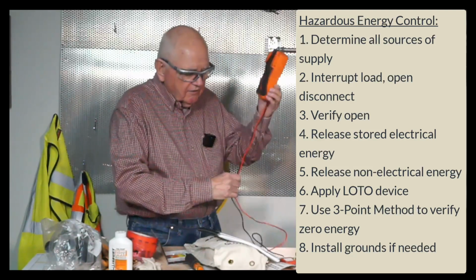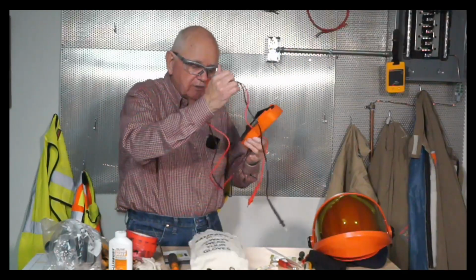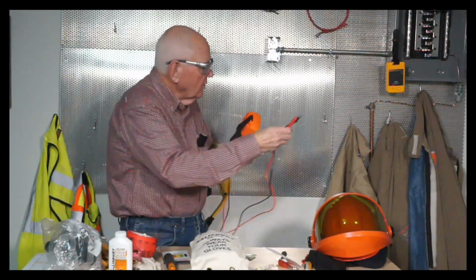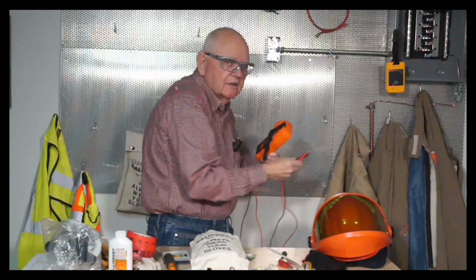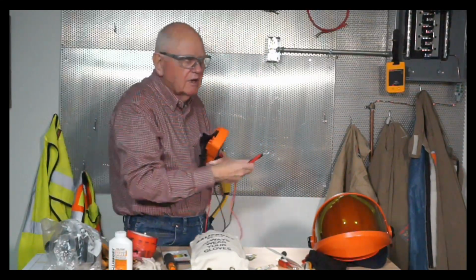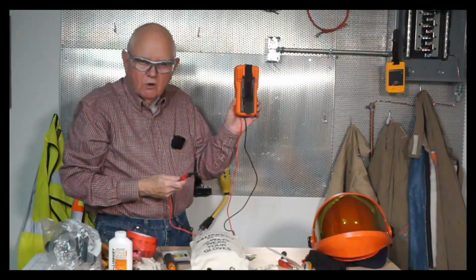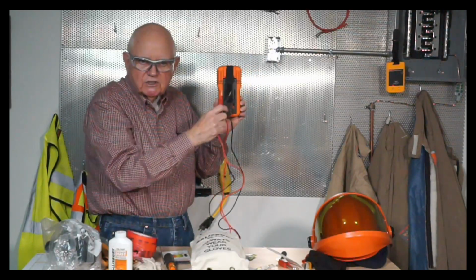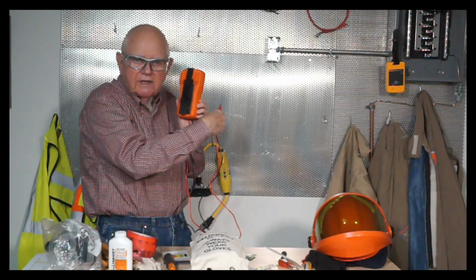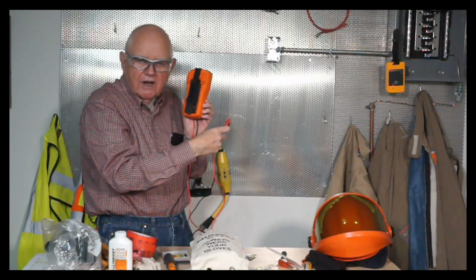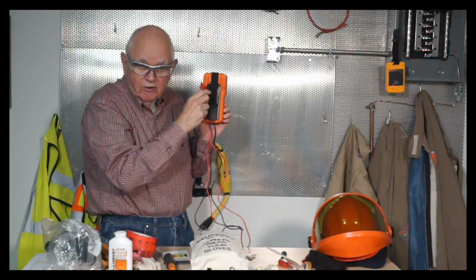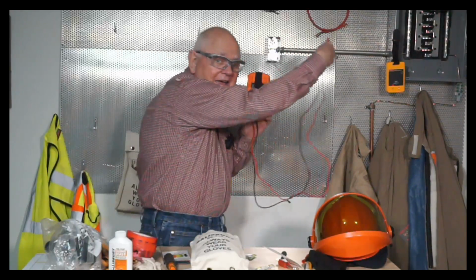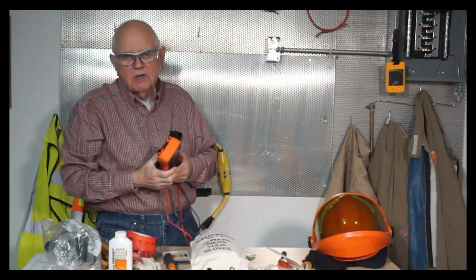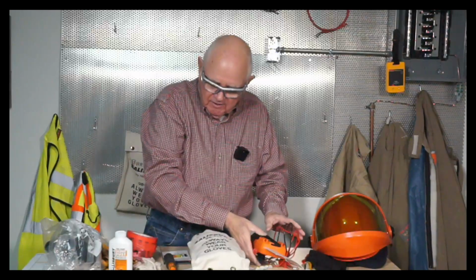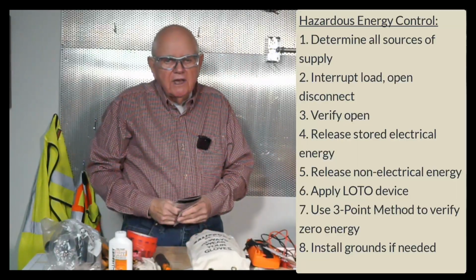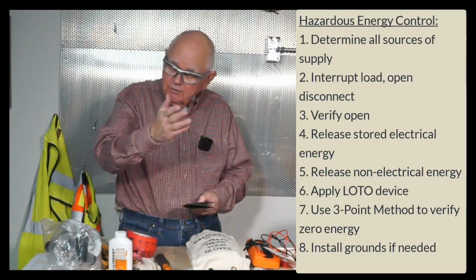And that's where you use that 3-step method, right? And a little bit of what we talked about earlier. I go through and I use my proving unit. In this case, I would go through and use my proving unit and make sure that my meter works. So I check a known source of voltage, make sure my meter works on voltage. Then I go in and I verify phase to phase and phase to ground that I have zero energy according to my meter. Then I go back to my known voltage source and make sure that my meter still works on voltage.